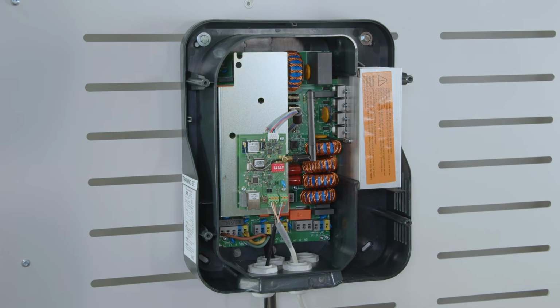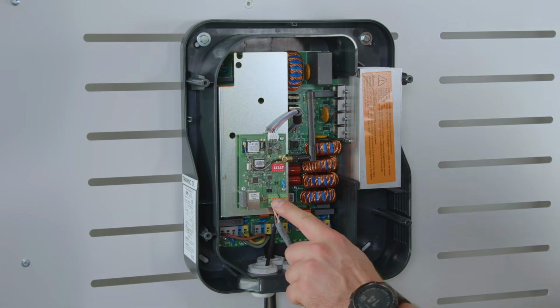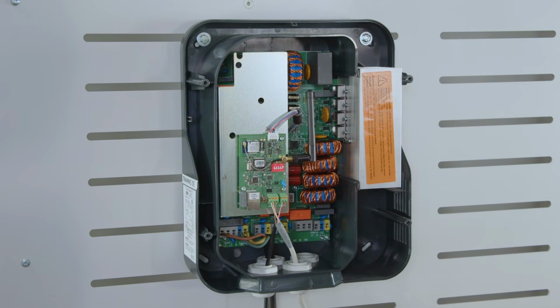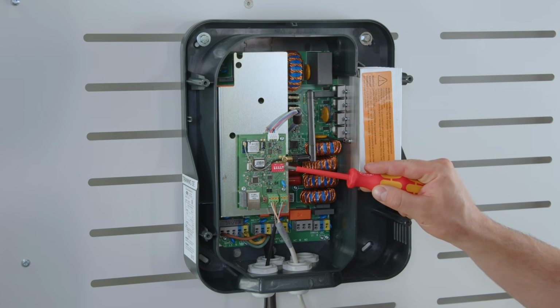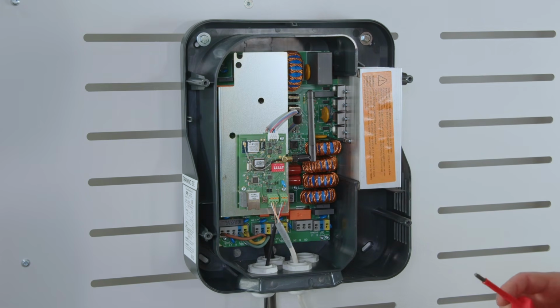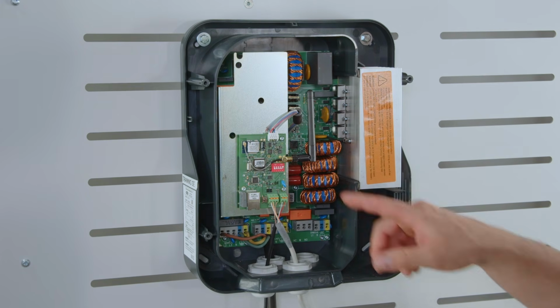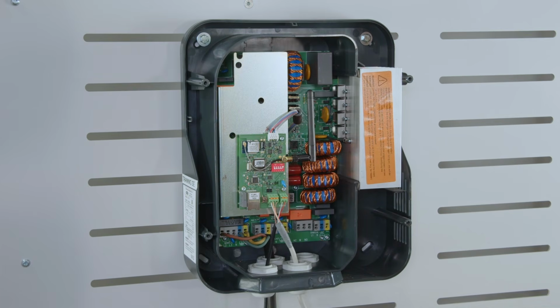So this is the end component, and therefore we need to set the 120 ohm resistance to the top position, to on. If we would have a second pair of cable in here and would go to another Fronius Smart Meter or to any other component, then we would need to switch this to off. This is the only scenario where we would have to switch this to off. As standard shipped, this would always be activated.